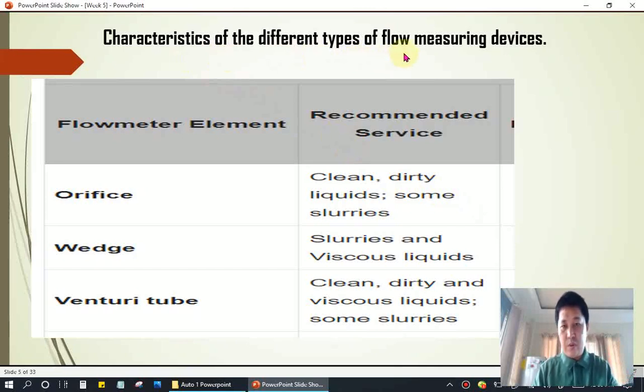So we have examples of flow meters. We have orifice type, wedge type, venturi tube type. So for orifice type, this is used for clean and dirty liquids, some slurries. Wedge type, slurries and viscous liquids. So viscous liquids are lube oil and marine fuel oil. So they are viscous liquids.